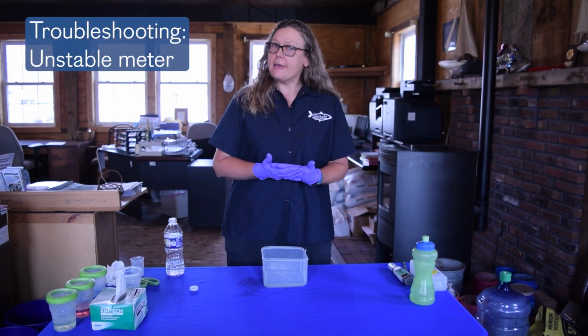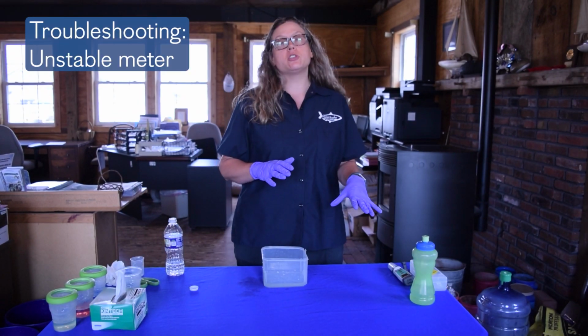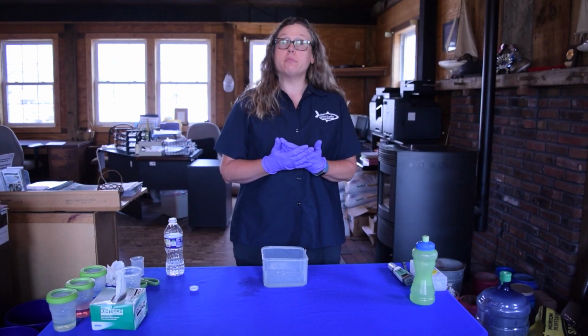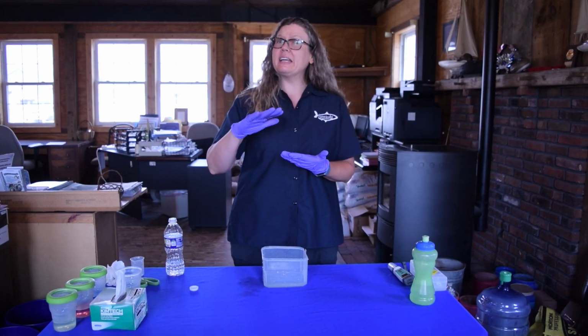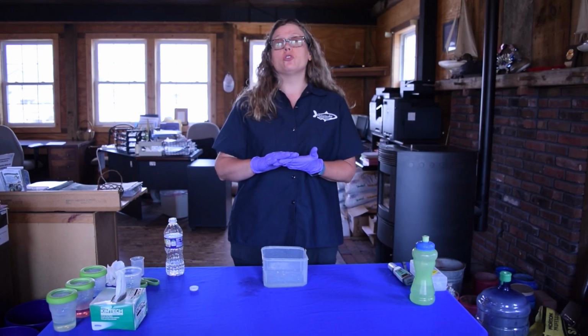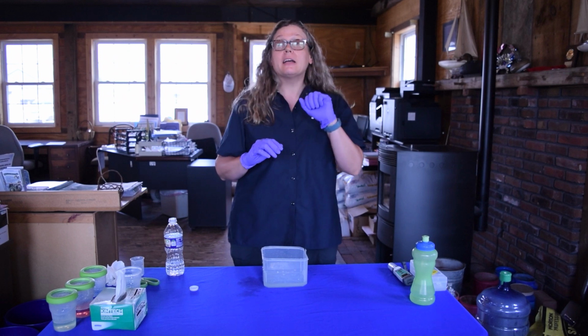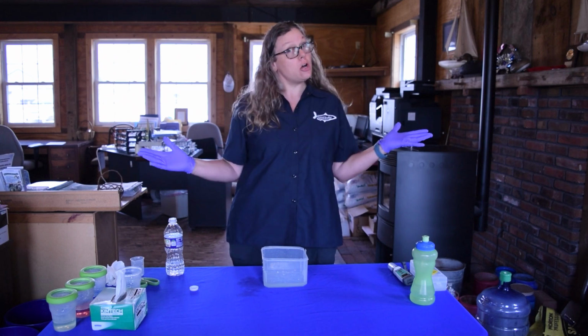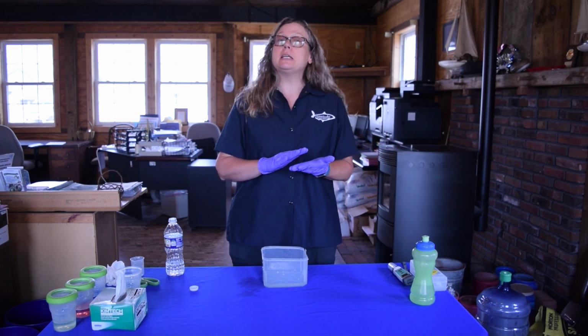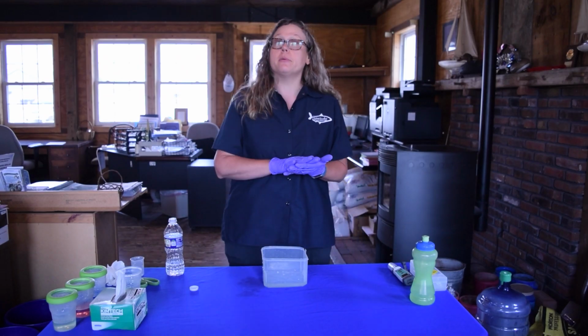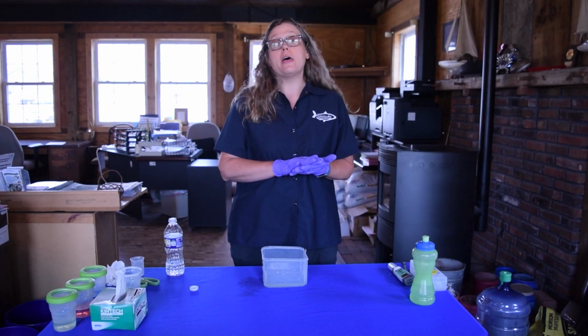So if you're in the field and your pH meter will not stabilize, so that means that the reading continues to drift, you're maybe only getting a blink of a smiley face or maybe no smiley face at all, that means that you need to contact staff immediately so that we can get you a replacement meter.